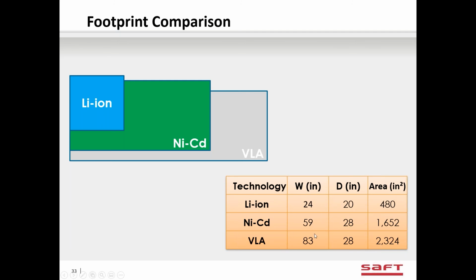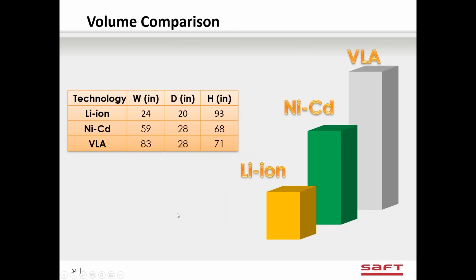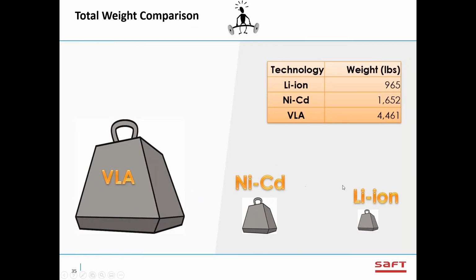And then you can see the comparison. So versus lead acid, that's even smaller than 25% of the footprint. Of course, that's because we stacked it double high. If I don't have the room for that, I have a smaller cabinet, and that would take 2 of those, so it would be 48 inches by 20 inches. On the volume comparison, again, you can see the lithium is much smaller in the volume. The weight is significant. We're about 25% of the weight of lead acid.